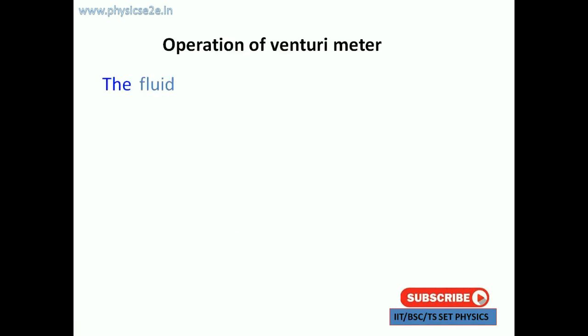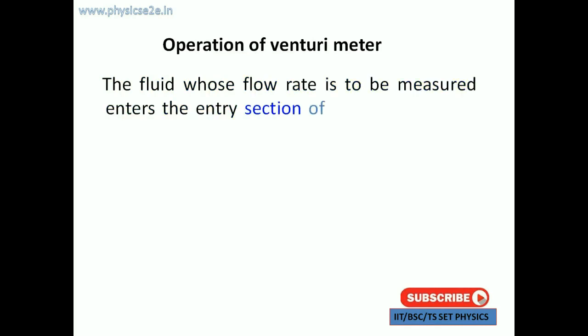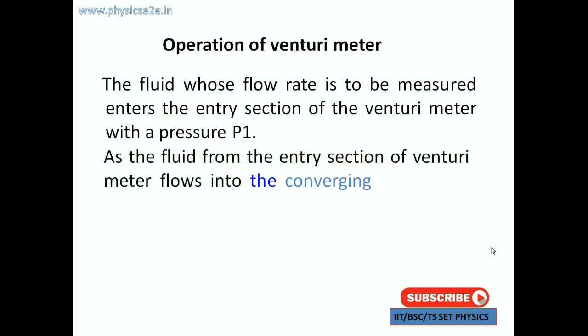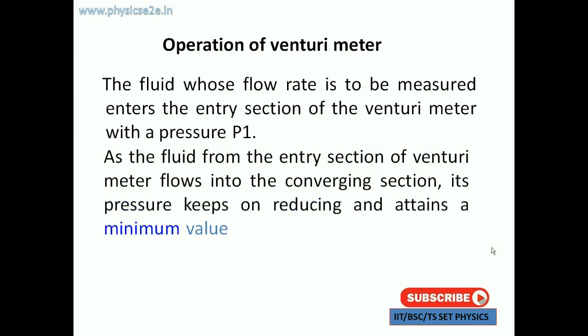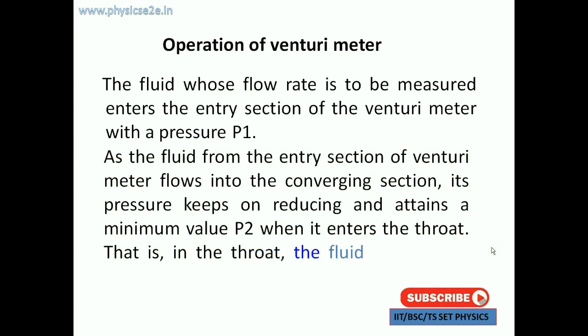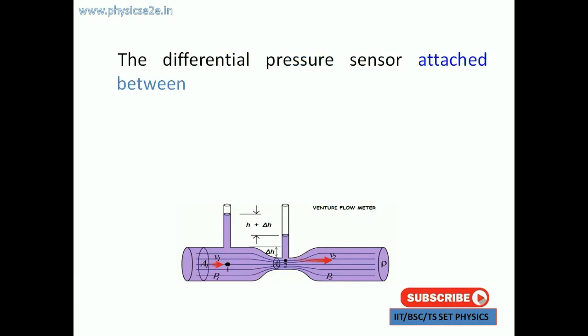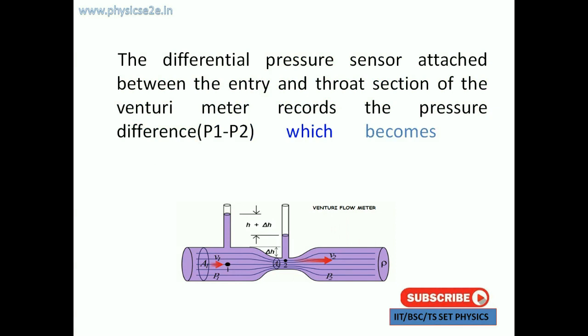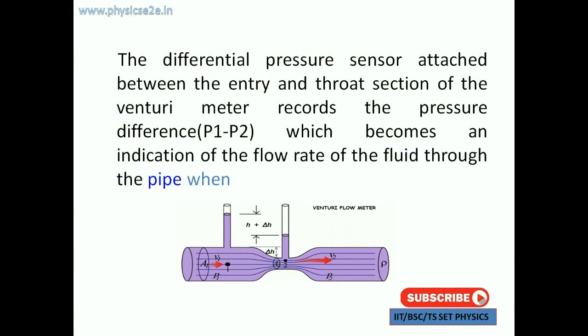Operations of the Venturi meter: the fluid whose flow is to be measured enters the inlet section of the Venturi meter with pressure p1. As the fluid flows into the converging section, the pressure keeps on reducing and attains a minimum value p2 when it enters the throat. The differential pressure sensor attached between the entry and throat section records the pressure difference p1 minus p2, which becomes an indicator of the flow rate of fluid through the pipe when calibrated.